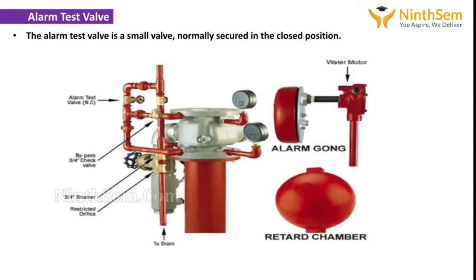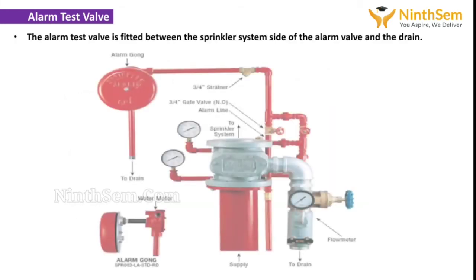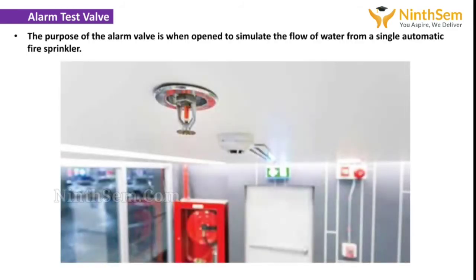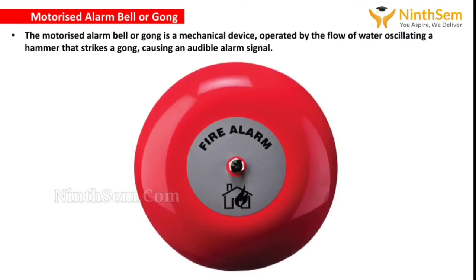Next, the alarm test valve. The alarm test valve is a small valve normally secured in the closed position. The alarm test valve is fitted between the sprinkler system side of the alarm valve and the drain. The purpose of the alarm test valve is, when open, to simulate the flow of water from a single automatic fire sprinkler. Next, the motorized alarm bell or gong. The motorized alarm bell or gong is a mechanical device operated by the flow of water oscillating a hammer that strikes a gong, causing an audible alarm signal.